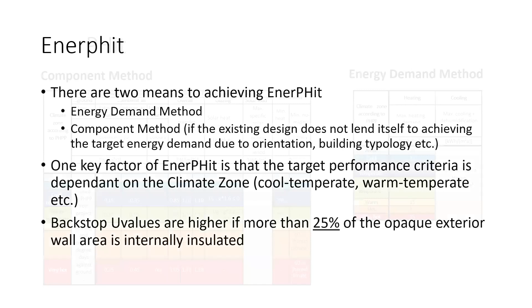So this is your performance criteria for your component method and for your energy demand method. And notwithstanding that, you have a target air tightness level, and your N50 of 1 air change has to be achieved to meet any of your EnerPHit standards. So you can see that in your component method there's a lot of criteria that you have to meet if you are going that route, whereas your energy demand method is effectively air tightness and your max heating demand.